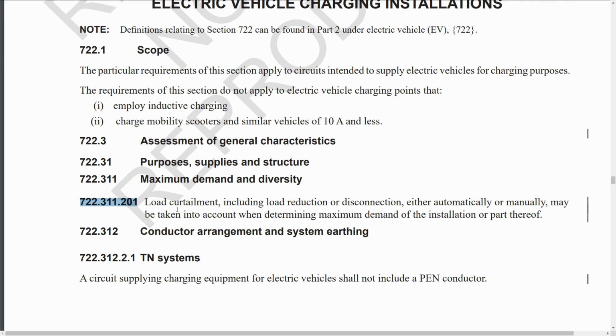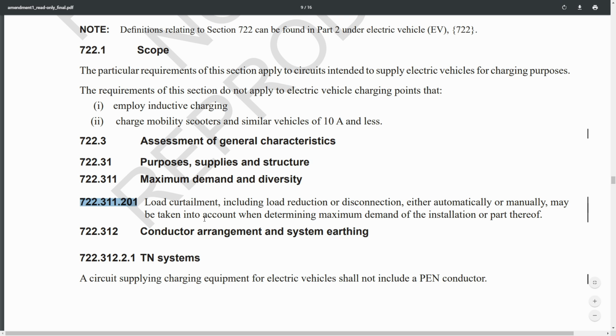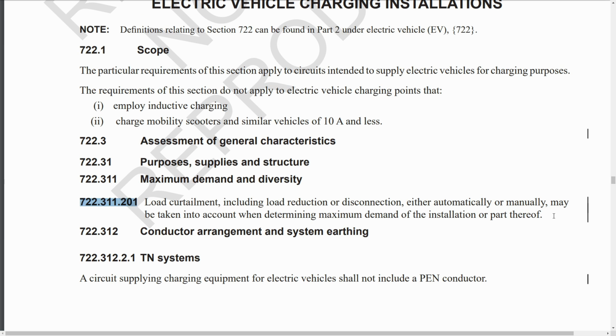722.311.201, which is load curtailment, including load reduction or disconnection, either automatically or manually, may be taken into account when determining maximum demand of the installation or part thereof. Now what this means is that the previous version basically stated that you can only have the maximum load current for each charging point and you can't apply diversity or anything like that. But now this is indicating that you can buy charging equipment which can monitor the total load on the installation, and you can program in at the installation point how much load is allowed to be taken for the whole installation.